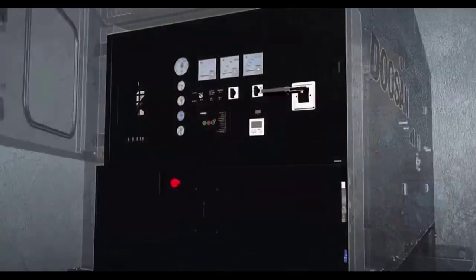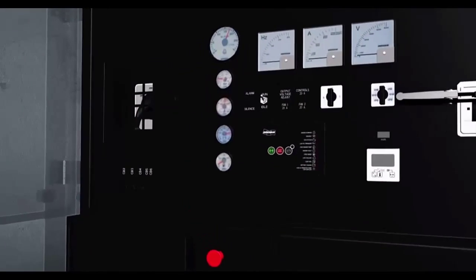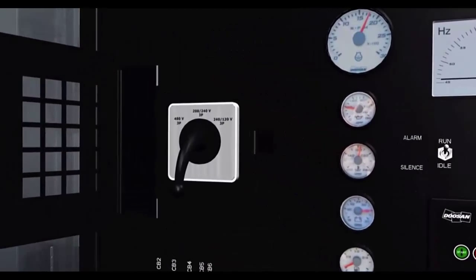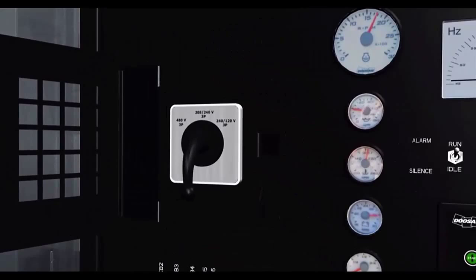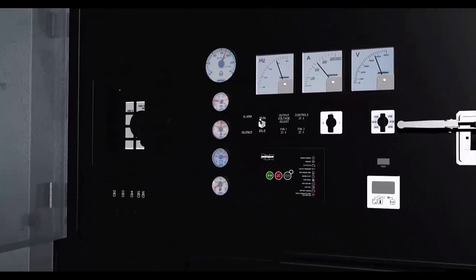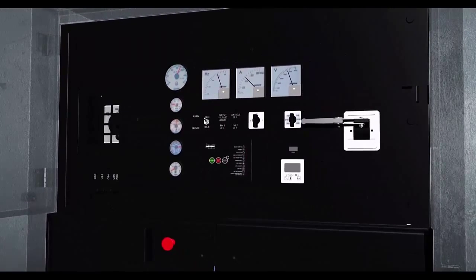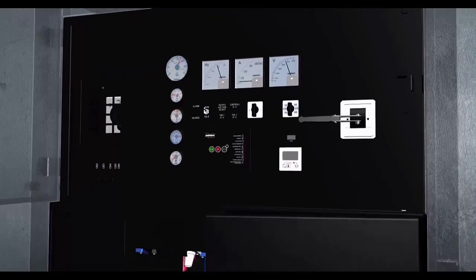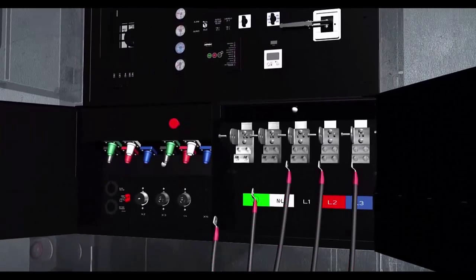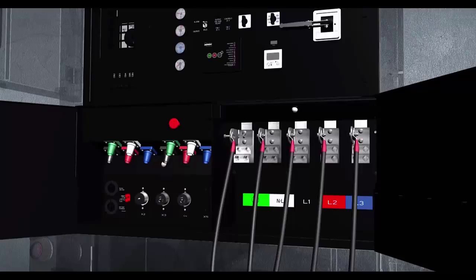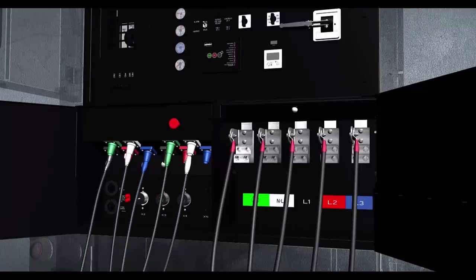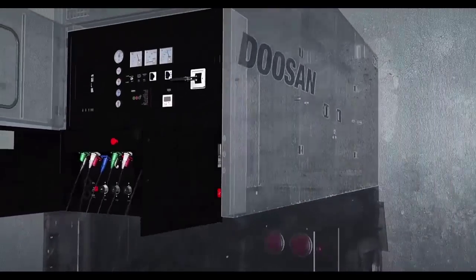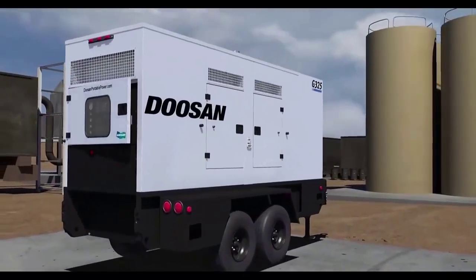To simplify wire connections, Doosan mobile generators have a convenient selector switch. When an operator selects the desired voltage, the switch adjusts the connections, and current flows through a protective device called a circuit breaker. If current exceeds capacity, the breaker halts the system, protecting the generator and connected equipment from potential damage. Once power reaches the connection panel, operators can attach power cables to the generator's terminal board, receptacle panel, or cam lock panel, transforming electrical energy into light, heat, or motion, providing the power we rely on every day.